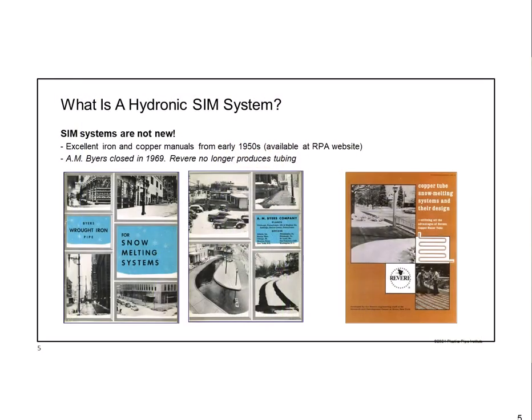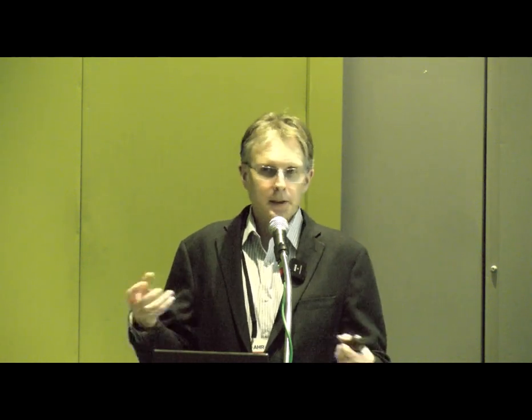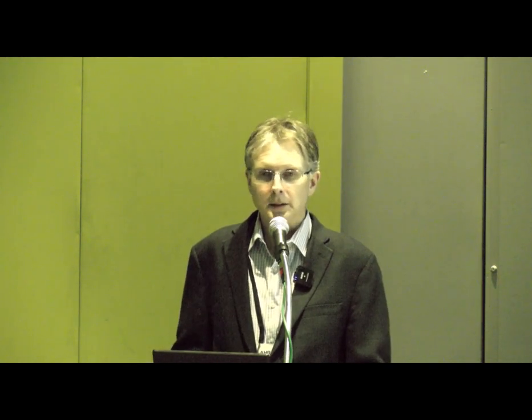What is a hydronic snow and ice melt system? If you're familiar with radiant heating, a lot of people think of snow and ice melt systems as outdoor radiant heating systems, because you build them a lot like a radiant heating system—pipes encased in concrete or under outdoor surfaces, with warm liquid going through. But it's quite different from the design perspective, and it isn't just straight water in the pipes because that would freeze. So it's water with antifreeze mixed in to prevent freezing when you're not running the system.